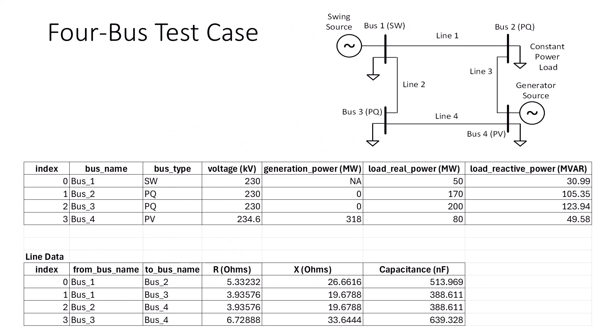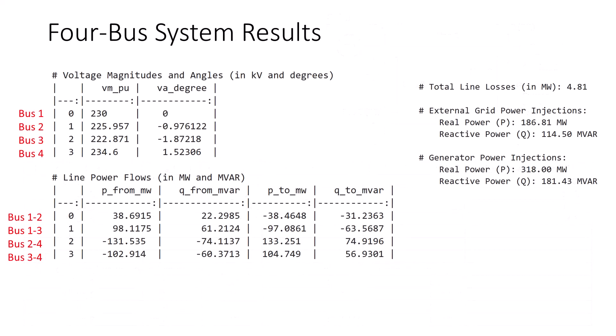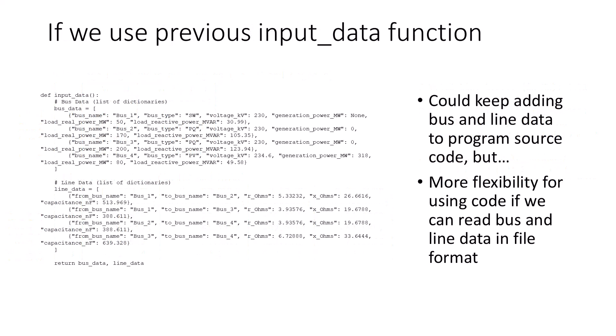We will test our program code using this four-bus test case. This is from Chapter 9 of the textbook Power System Analysis by Grainger and Stevenson. Bus type SW denotes a swing bus, which is an ideal voltage source. PQ denotes a load bus, and PV denotes a generation bus. The bus voltage KV field provides a swing bus voltage, as well as the generator PV bus voltage magnitude set point. Here is a solution for this four-bus system test case. These results were obtained using a pre-existing Power Flow program.